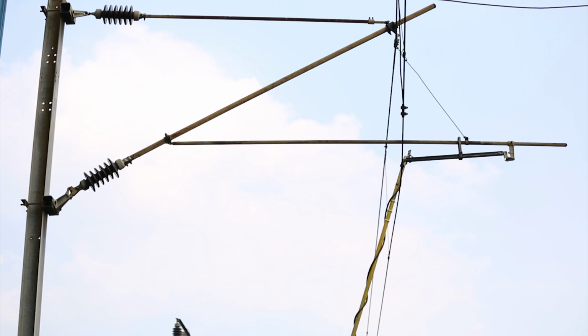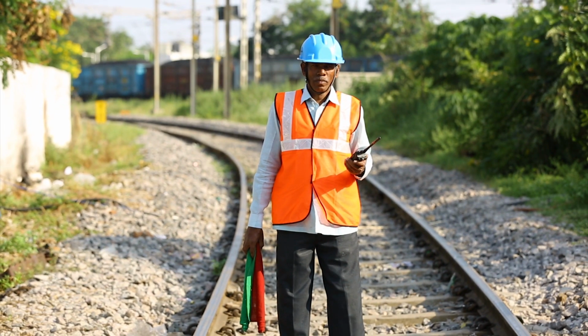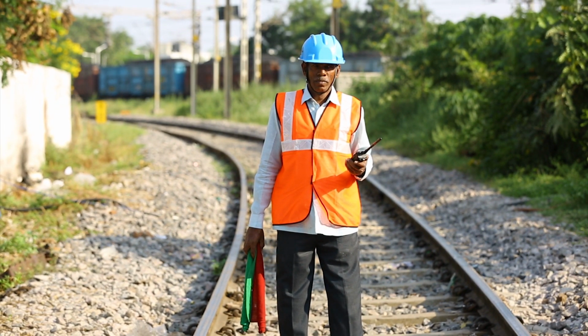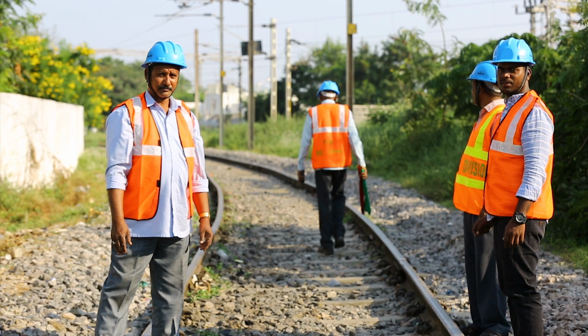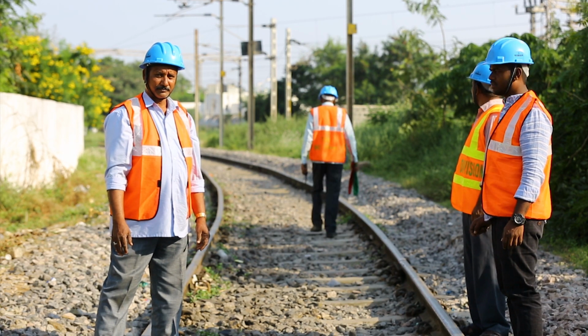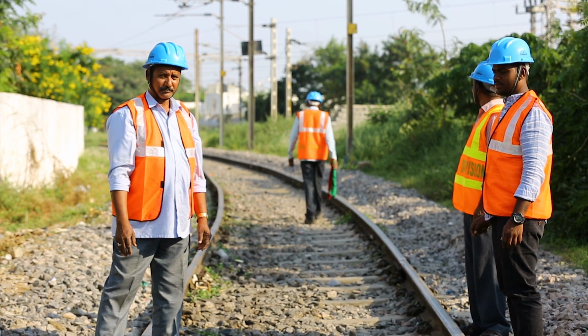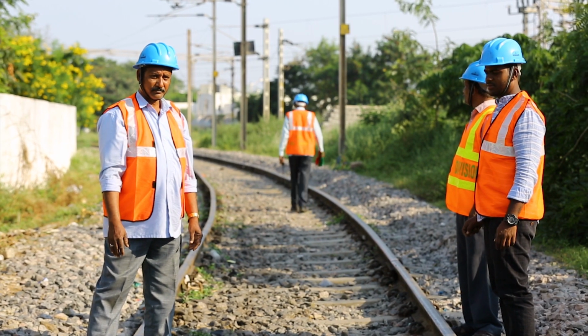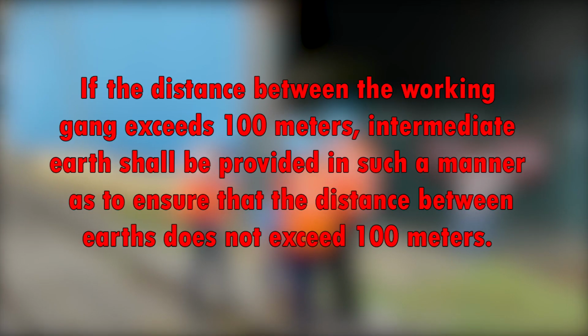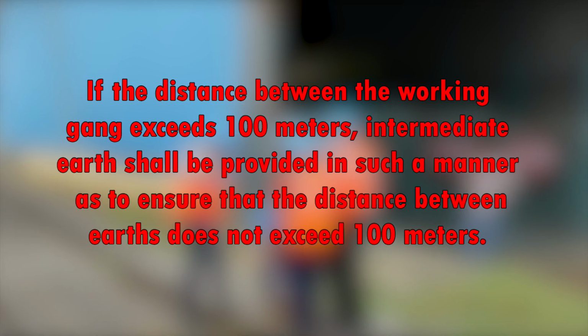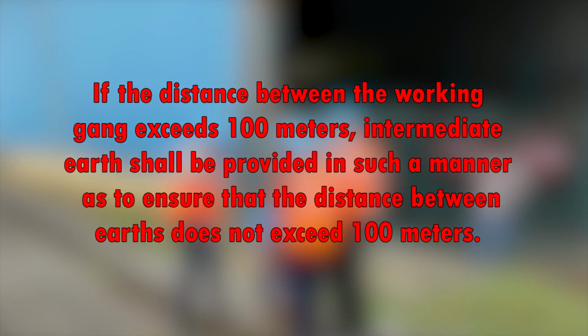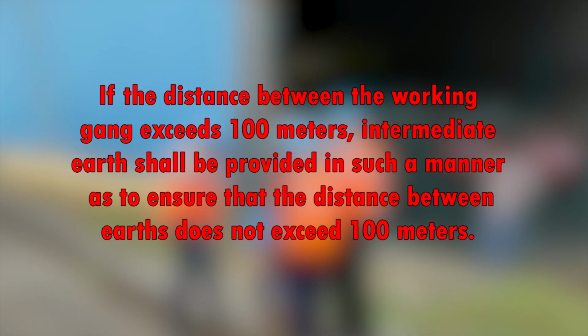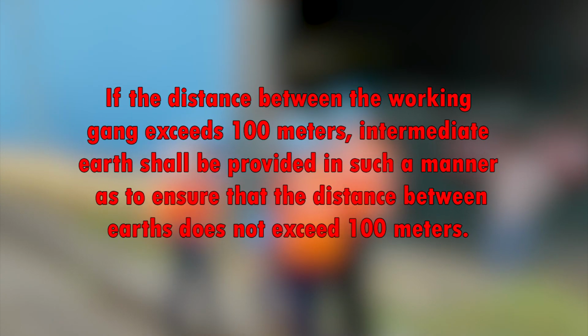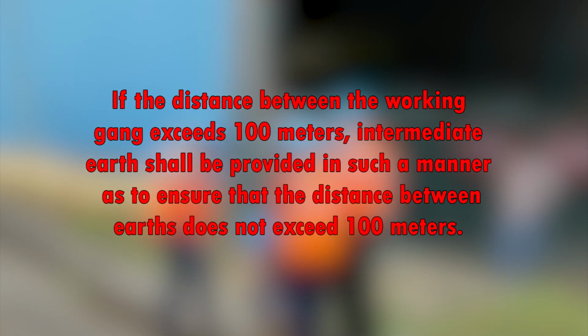Each working gang shall be protected by at least 2 independent earths, one on each side. Men shall be deputed on both sides of the site of work to warn the working party of any approaching train on the same track and adjacent track. If the distance between the working gang exceeds 100 meters, intermediate earths shall be provided in such a manner as to ensure that the distance between earths does not exceed 100 meters.